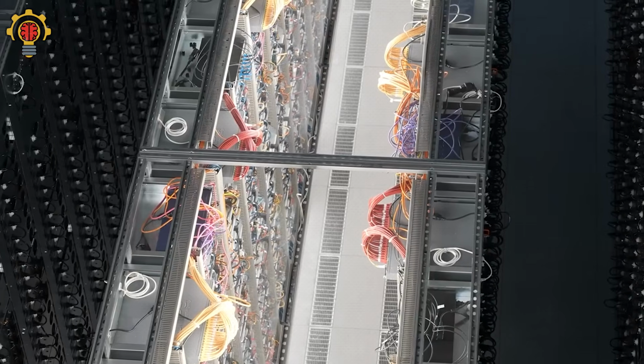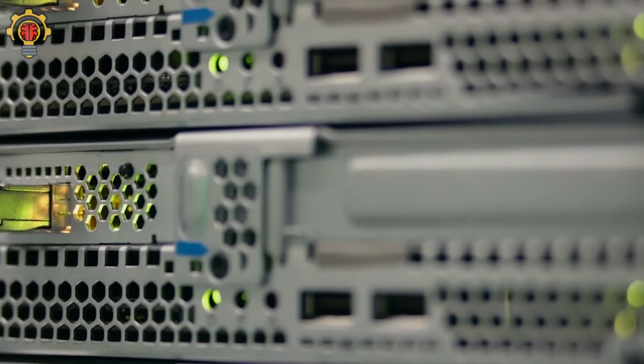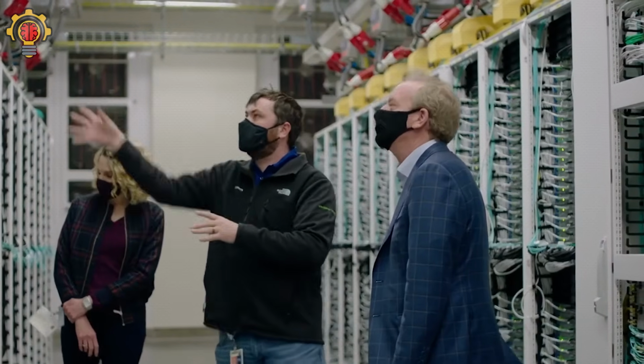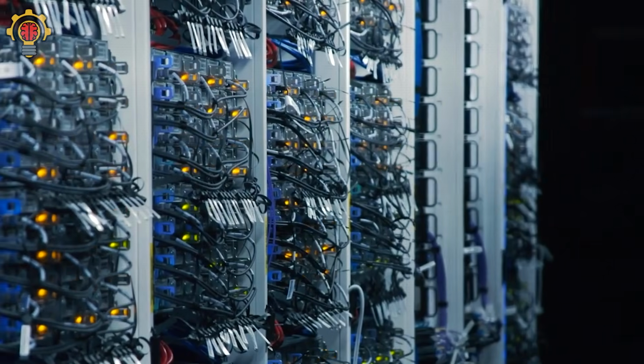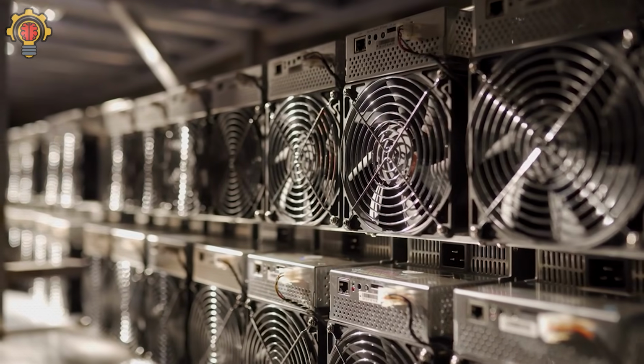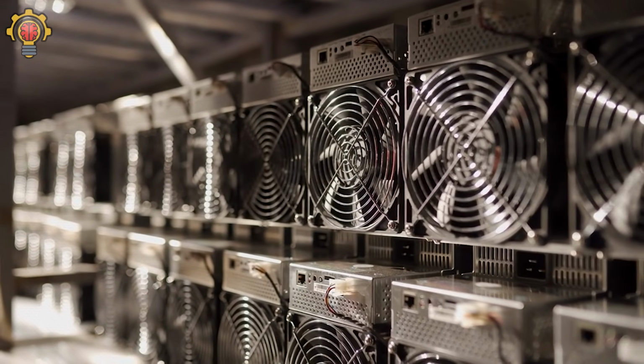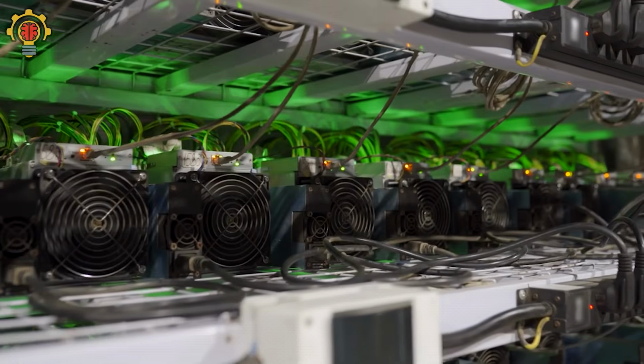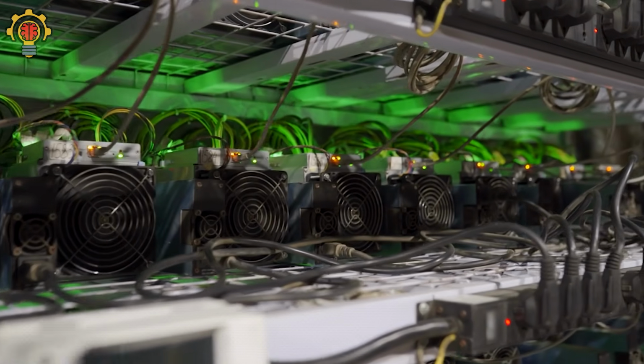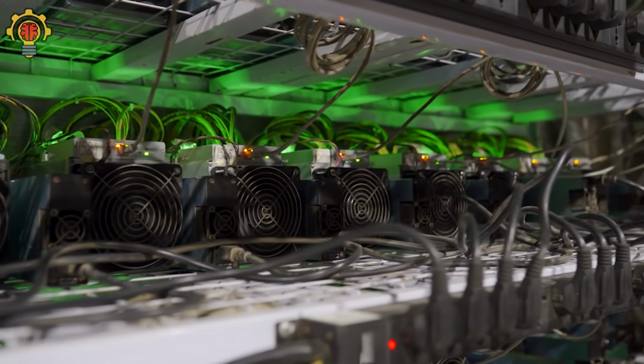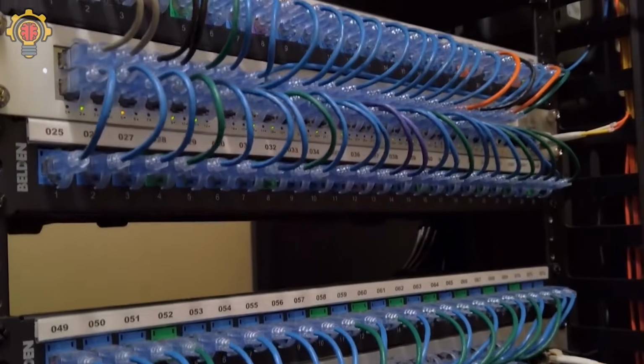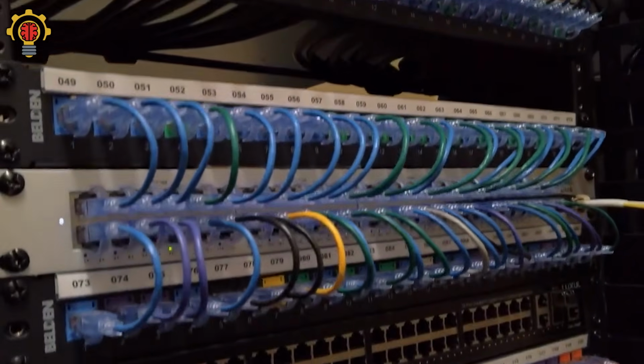And that is where the industry began turning towards something that once sounded impossible: liquid cooling. At first, the idea feels dangerous. Computers and liquids normally do not mix well. But surprisingly, liquid transfers heat far better than air. In fact, liquid can carry several times more thermal energy than the same amount of air. That makes liquid cooling incredibly effective for high-density computing.